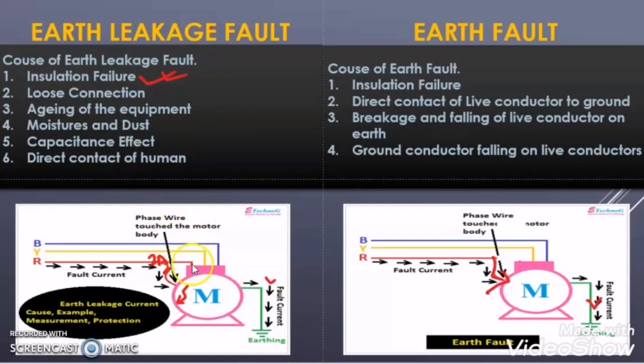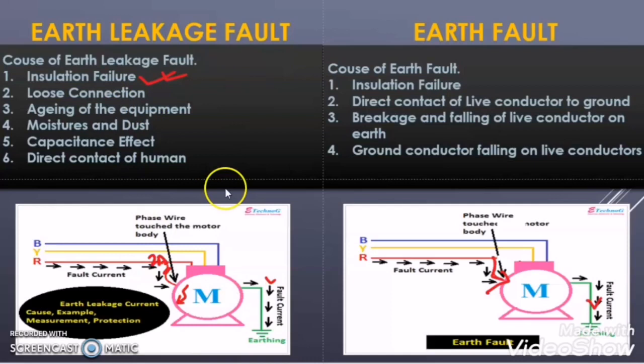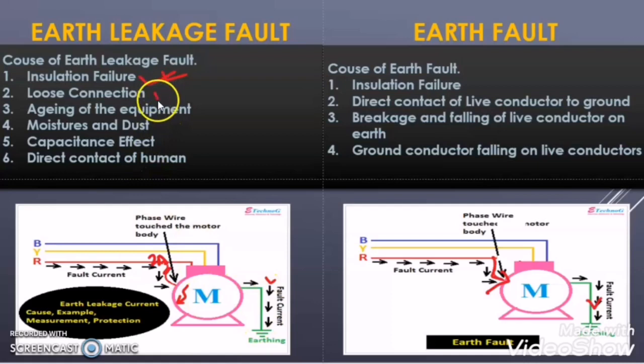The second reason is loose connection. Suppose in the terminal box of the motor we terminated R phase, Y phase and B phase, but the connection is not tight — it is loose. Then due to the loose connection the phase wire may be touching the motor body and causing the earth leakage fault condition. In this case the motor winding will have current, but due to the loose connection some amount of current will flow through the body of the motor and then to the earth. So loose connection is also one of the causes of earth leakage fault.